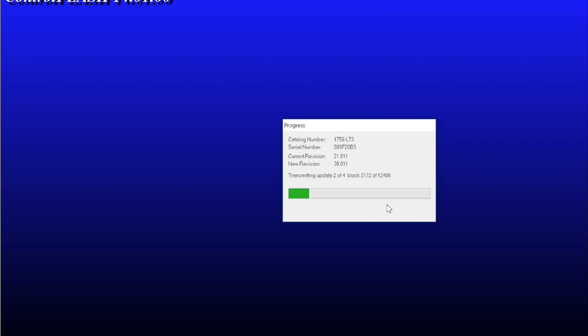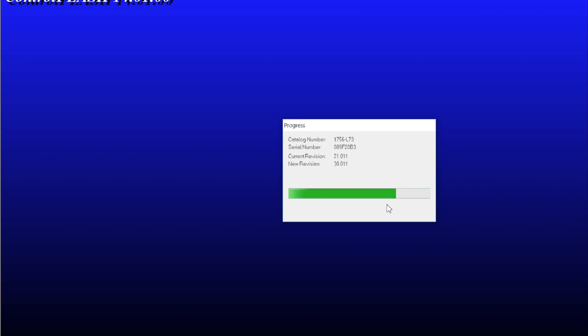A couple of things as this is taking place. It's best practice to put the key switch into the program mode. That will allow you to update the firmware even if there's a fault in the current controller. If you leave it in remote or run, you won't be able to update the firmware. So be aware of that.